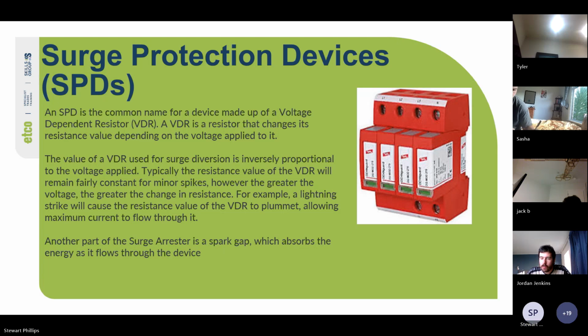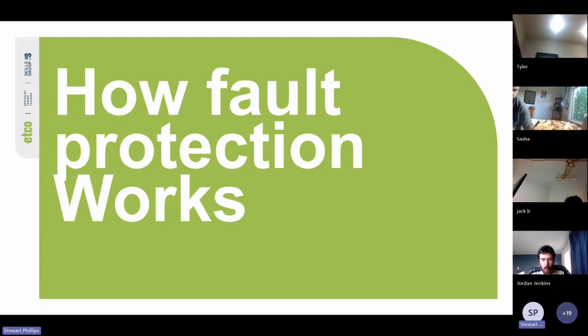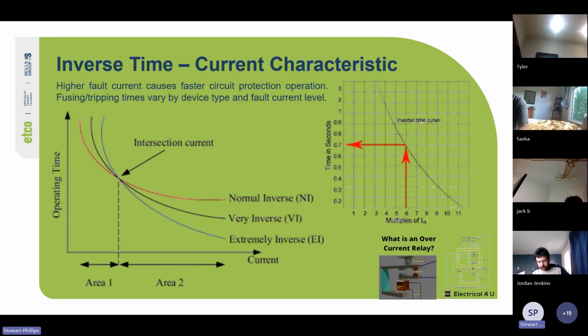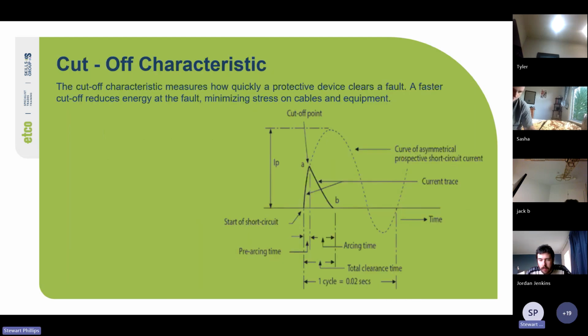Yes, cool. So now we'll look at how fault protection works. Fault protection works on a number of factors. But here, the inverse time current characteristics. Basically, the higher the fault current, the faster the circuit protection operates. Fusing and tripping times vary by device type and fault current level, but they tend to follow the inverse graph. So the operating time goes down as the current increases. You increase one, you decrease the other. You decrease one, you increase the other. So more current, faster trip time, but obviously up to a point where it can no longer protect against it. Cool.